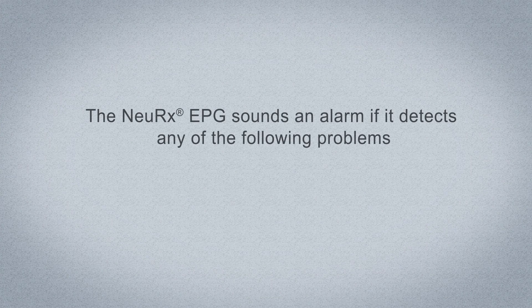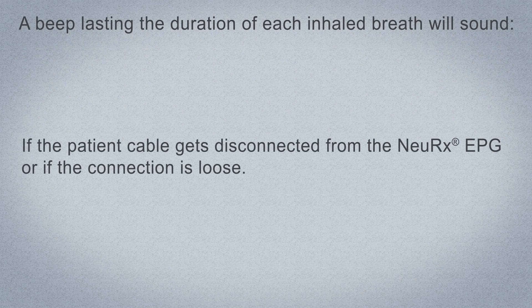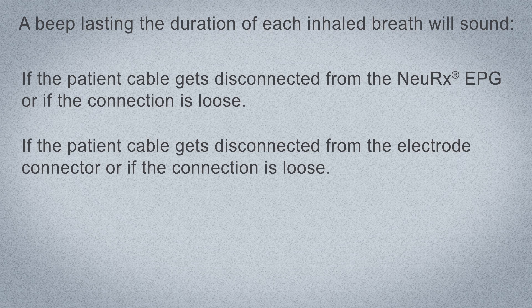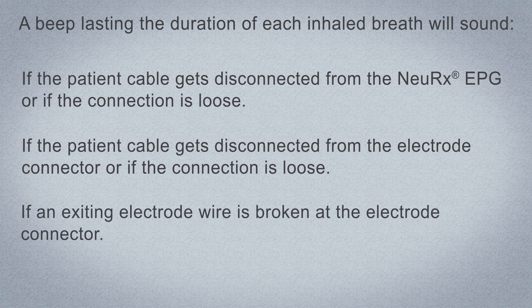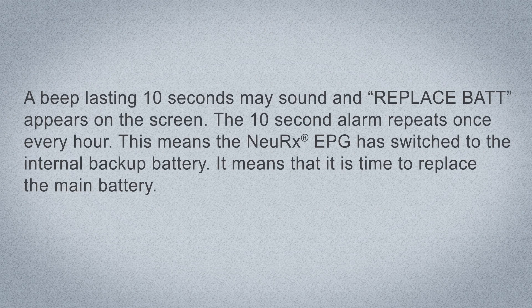Alarms. The NeuRx EPG sounds an alarm if it detects any of the following problems. A beep lasting the duration of each inhaled breath will sound if the patient cable gets disconnected from the NeuRx EPG or if the connection is loose, if the patient cable gets disconnected from the electrode connector or if the connection is loose, or if an exiting electrode wire is broken at the electrode connector. The alarm will repeat until the problem is resolved. A beep lasting 10 seconds may sound and 'Replace Batt' appears on the screen, repeating once every hour — this means the NeuRx EPG has switched to the internal backup battery.